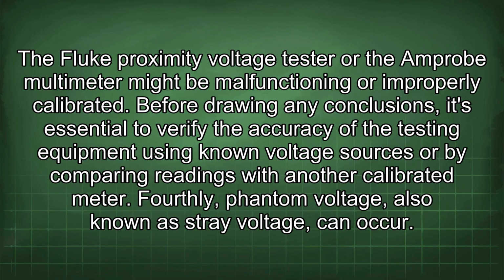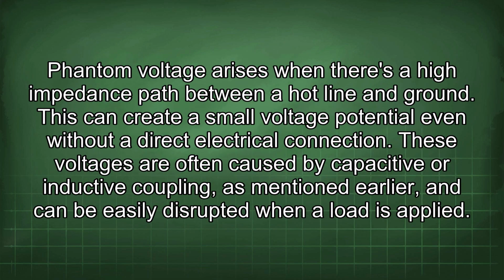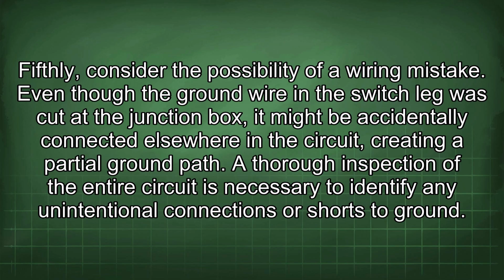Fourthly, phantom voltage, also known as stray voltage, can occur. Phantom voltage arises when there's a high impedance path between a hot line and ground. This can create a small voltage potential even without a direct electrical connection. These voltages are often caused by capacitive or inductive coupling, as mentioned earlier, and can be easily disrupted when a load is applied. Fifthly, consider the possibility of a wiring mistake.